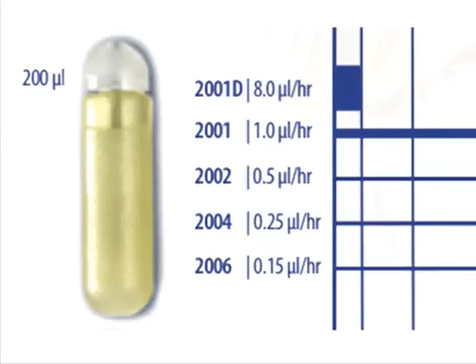Again, the 200 means 200 microliter volume, and the last 2 means 2 weeks. Notice that this pump infuses at 0.50 microliters per hour, twice as fast as model 2004. Because this pump infuses twice as fast, the concentration required in the pump will be cut in half. You'll need to ask yourself the same question, whether this new, reduced concentration is within the solubility parameters of your drug.